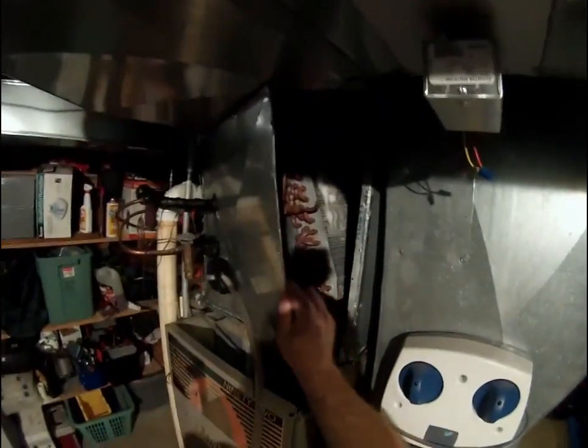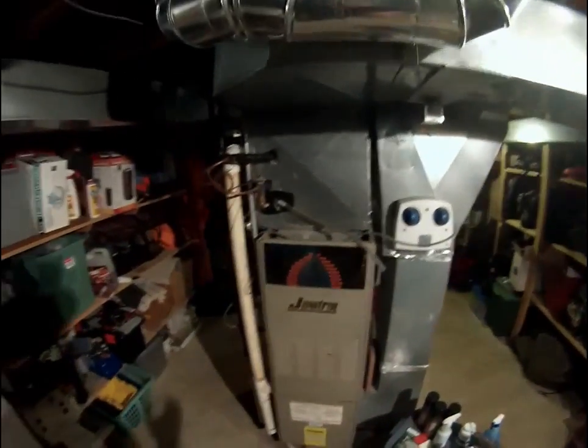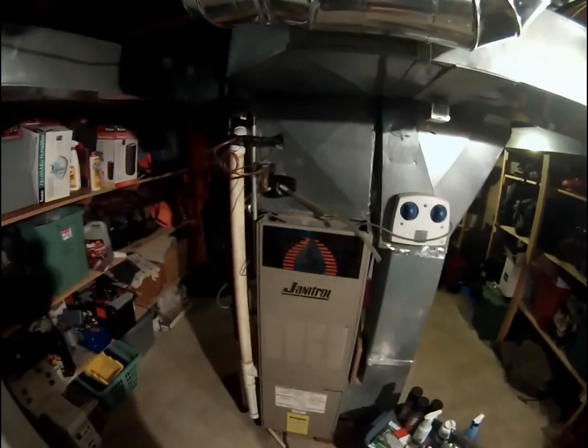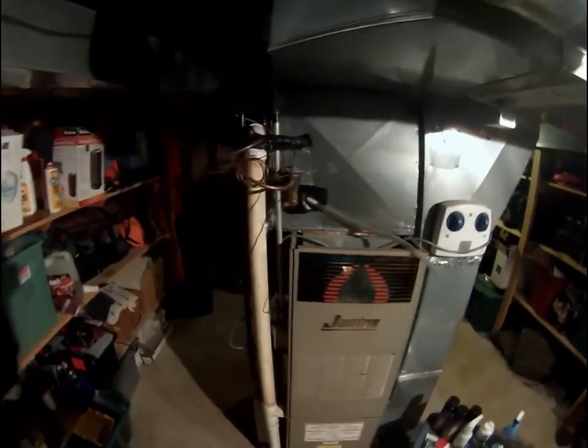So get your air conditioning coil real clean. Make sure that coil down there is clean. Make sure all your registers are open in the house. Sometimes somebody moves out of the house and you close a bunch of registers. That'll cause it to freeze too.